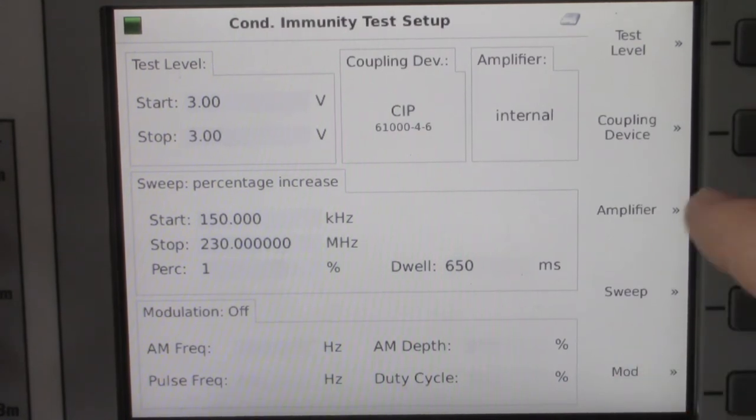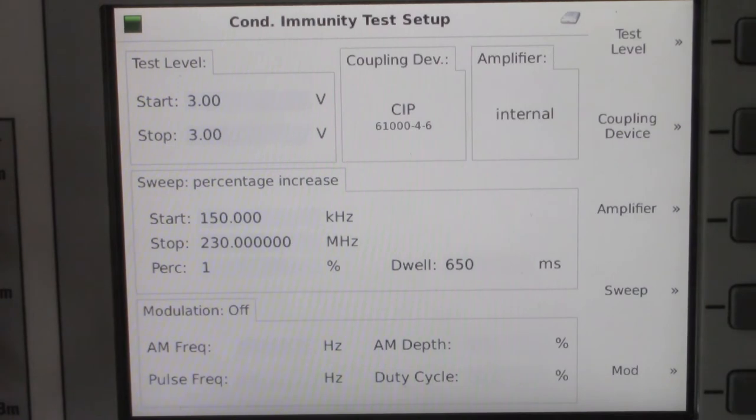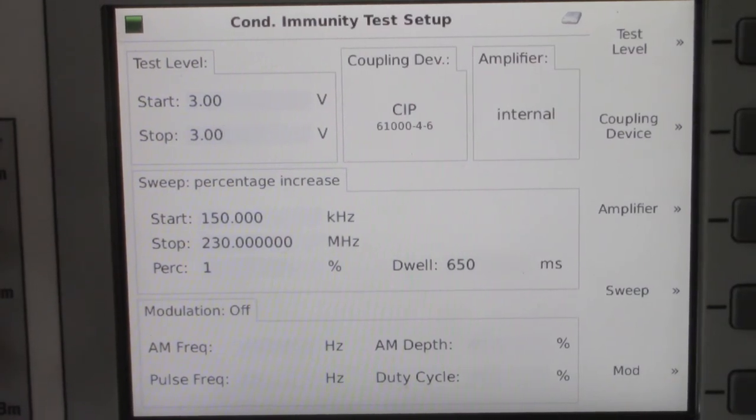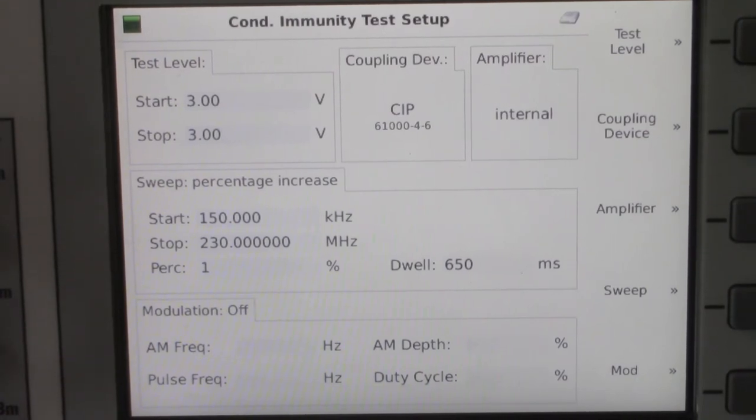One more thing to be aware of is the amplifier right here. It says internal. Right now we're using the 80 watt amplifier from 150 kilohertz to 230 megahertz, which is built inside the Teseq NSG 4070.